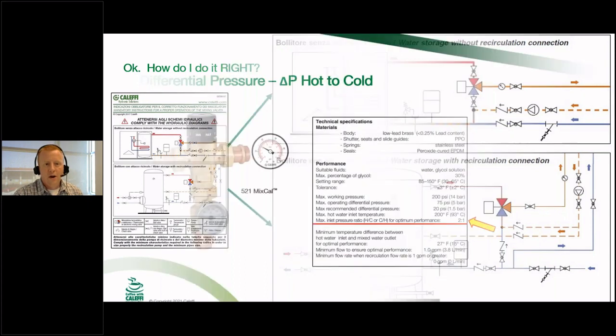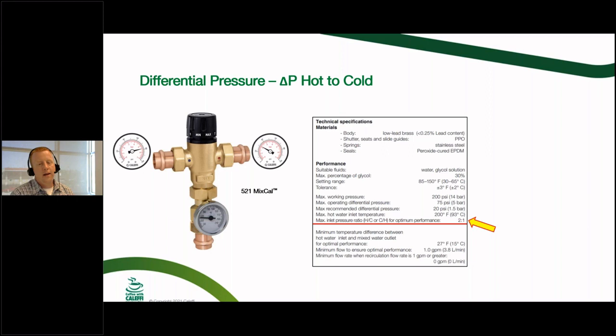So the next thing that we wanted to talk about is going to be differential pressures. And this is something that's called out in everybody's manuals for mixing valves. This is just a particular little snippet from our 521 series MixCal, where we call out the fact that you need to have a maximum inlet pressure ratio for optimum performance, or up to a maximum inlet pressure ratio between the hot and cold. Now, what does that mean? We call out a 2-to-1 there, okay? So let's take for round numbers that you've got 60 PSI coming into this house or this building or whatever the case may be, and somehow you're managing to get 25 PSI at the hot instead of 60 PSI like you've got at the cold. So you've got this disparity, this big difference here between the hot and cold inlet, and you are exceeding that 2-to-1, and that is obviously a problem.